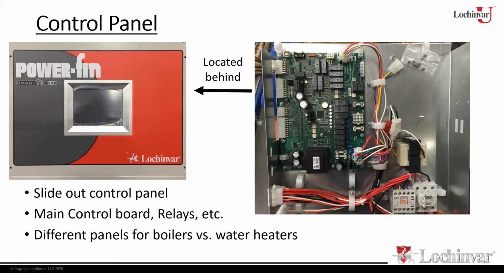So if I had a 5 million BTU boiler, that's what it's looking for. But I could take that board from that 5 million BTU boiler, put it in a 2 million BTU water heater, and it can work in that unit because it's going to look at that new plug. It's going to say, hey, do we really want to use this? If you accept it, it's going to find that parameter set for that particular control. And that's what it's going to go with.